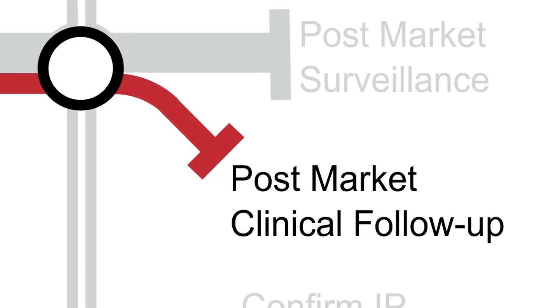A significant aspect of your post-market surveillance activities will be the planning, execution and reporting of clinical follow-up studies. These will typically look at things like safety and performance of the device, previously unknown side effects, emerging risks, and acceptability of the benefit-risk conclusion.